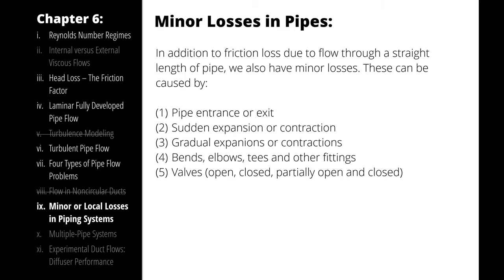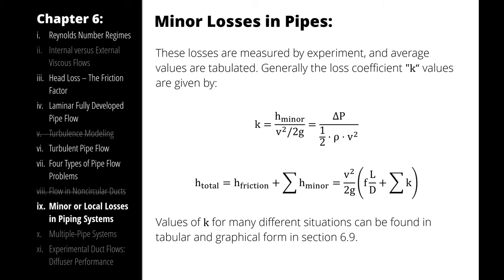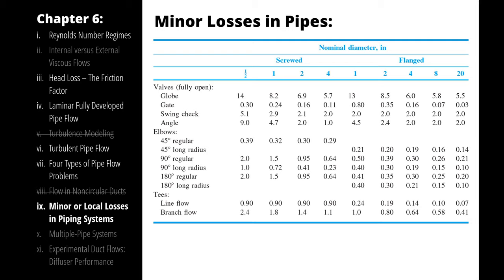These minor losses are referred to by what we call their minor loss coefficient, represented here with the letter K. In practice, you could consult the manufacturer for a published loss coefficient, or determine it yourself with a simple flow test. For our purposes here, we will be using the charts and graphs of general loss coefficients available in section 6.9 of our textbook, which give loss coefficients based on some of the physical characteristics of the fitting in question.